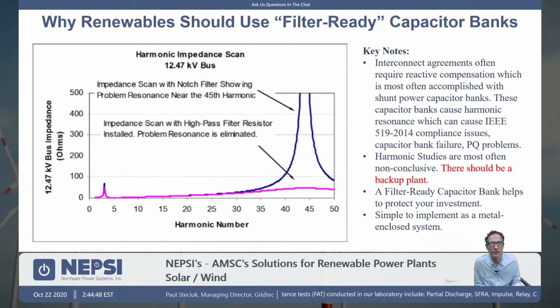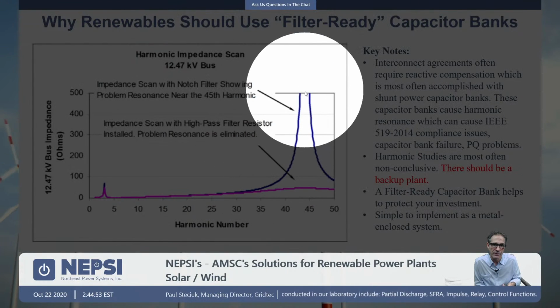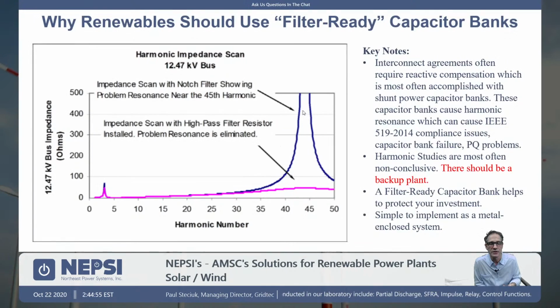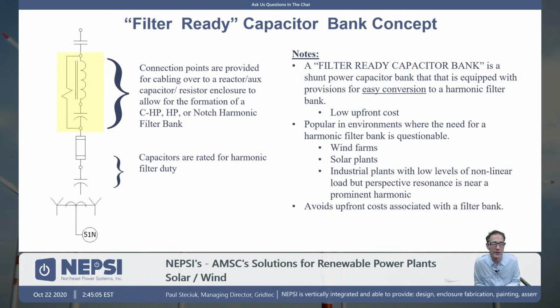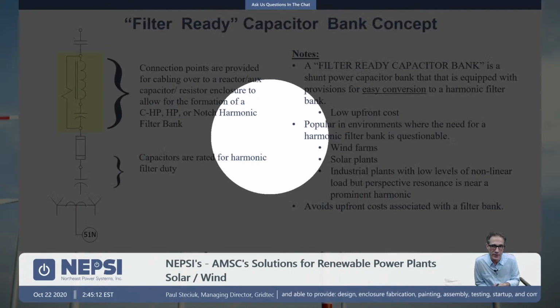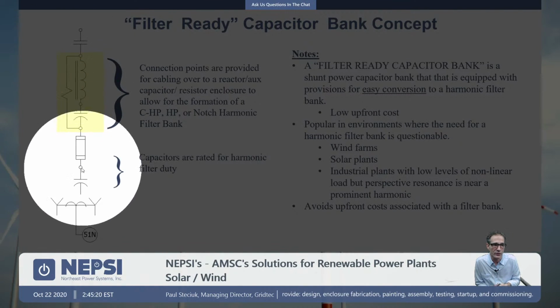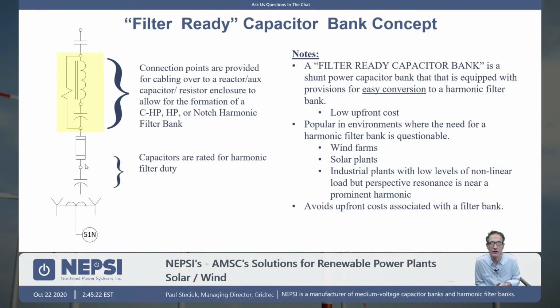Here I just want to talk about filter-ready cap banks for a moment. Remember, whenever you install a capacitor bank, you have resonant conditions, and because you have resonant conditions, you might need to install filters in the future. So whenever you install a cap bank in the renewables area, because the studies are not conclusive, NEPSI has a recommendation that you always install filter-ready cap banks. This area in yellow is what it takes to convert a standard cap bank here to a harmonic filter.